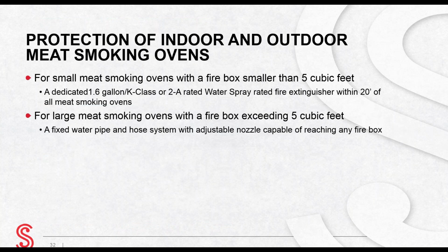What about protection of indoor and outdoor meat smoking ovens? There are requirements found in NFPA 96 Chapter 14. For small indoor and outdoor meat smoking ovens where the firebox does not exceed 5 cubic feet, you need a dedicated 1.6 gallon Class K or 2A rated water spray fire extinguisher within 20 feet of all meat smoking ovens. For large indoor and outdoor meat smoking ovens where the firebox exceeds 5 cubic feet, you will need a fixed water pipe and hose system with adjustable nozzle capable of reaching the firebox.